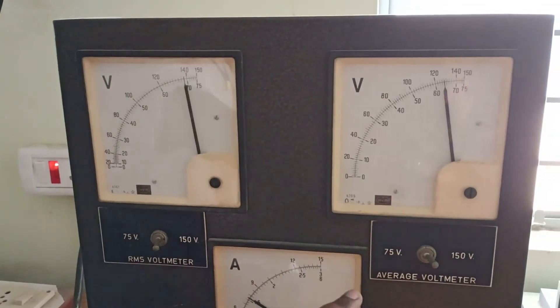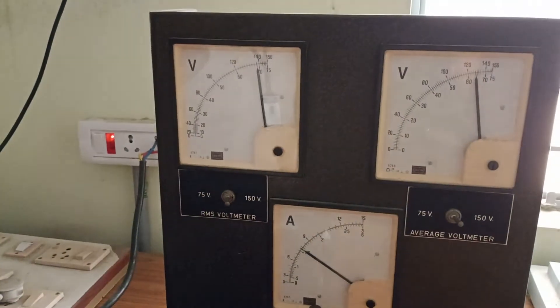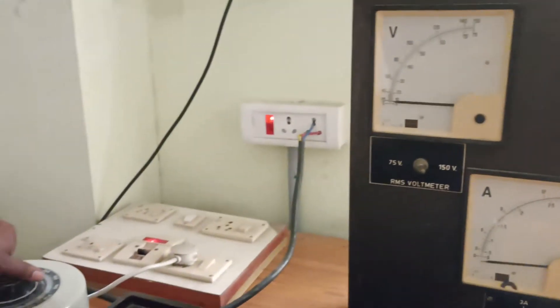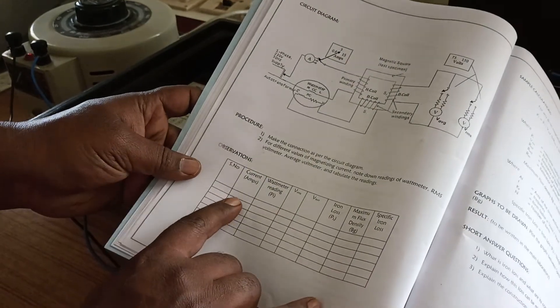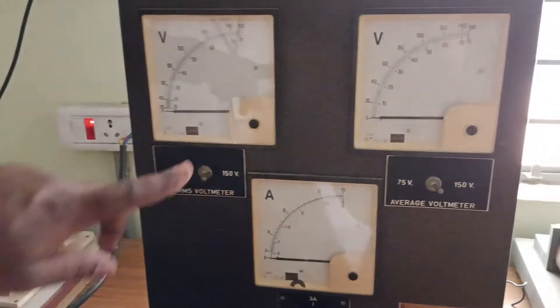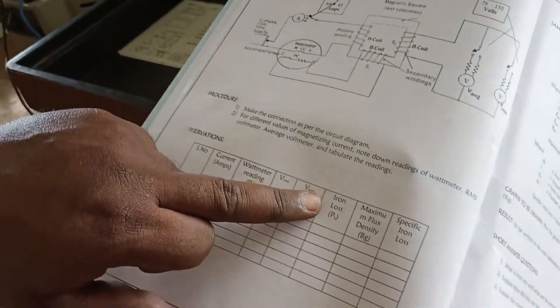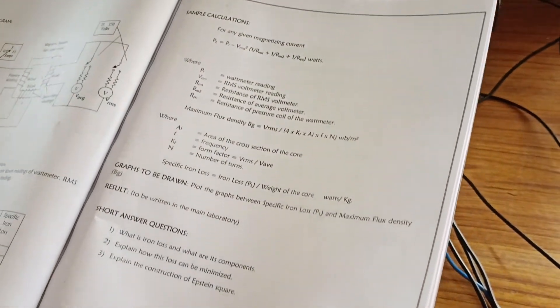At 1.5 amperes, the RMS voltage reads 140 volts and the average voltage reads 130 volts. In the tabular column, you note down the current from the ammeter, the wattmeter reading from the LPF wattmeter, V-RMS from the RMS voltmeter, and V-average from the average voltmeter. From these you can calculate the iron loss, maximum flux density, and specific iron loss using the given formulas. Thank you.